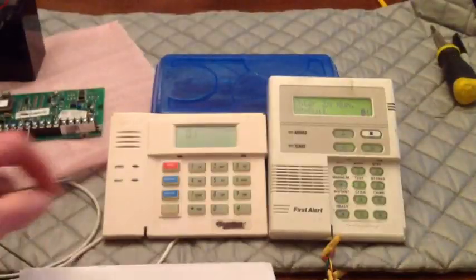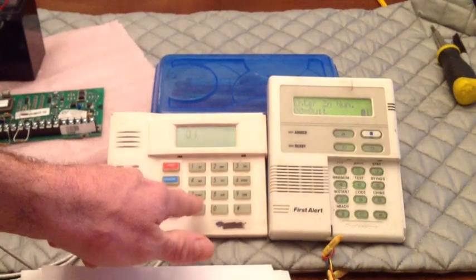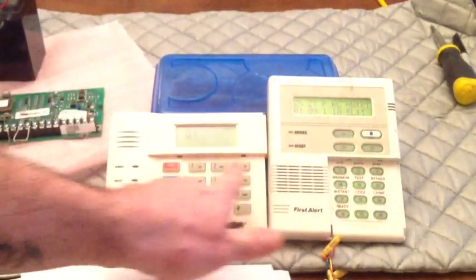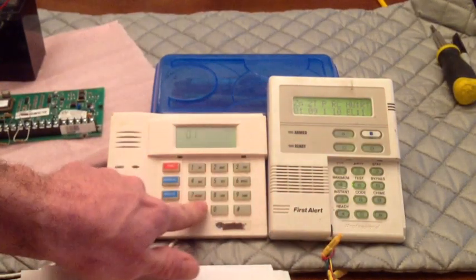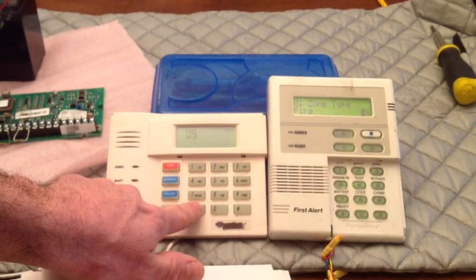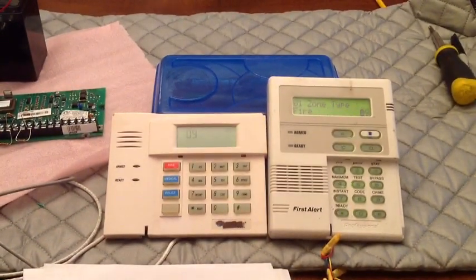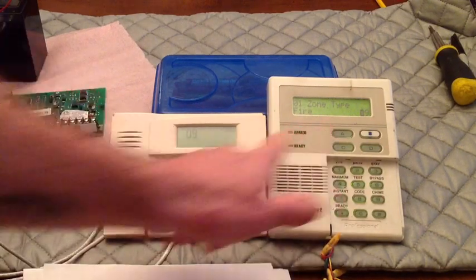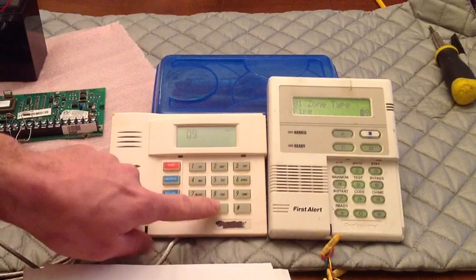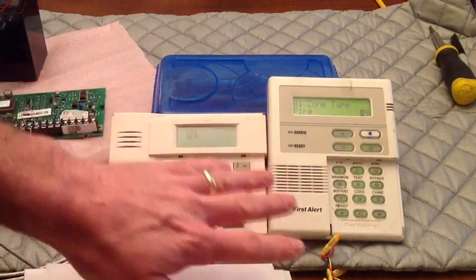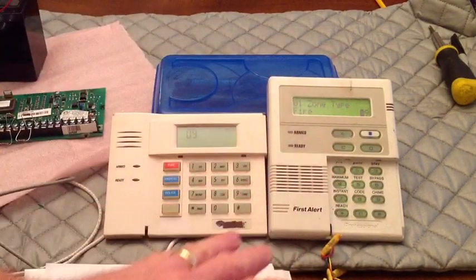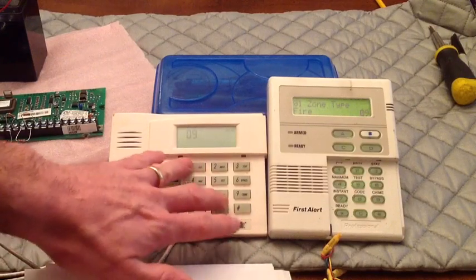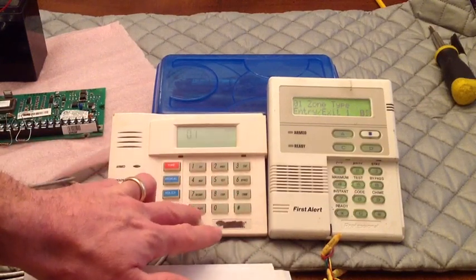So let's get started. Zone 1 shows what zone number. This is a summary screen. It's just going to still say 01. Zone type. That says, you know, right now it's 09, which is fire. That's what default on zone 1 is. We're going to, you can change it, leave it. Whatever zone you put on zone 1, you'd want to put the corresponding type to. We'll go ahead and just put it as a 01 entry exit.